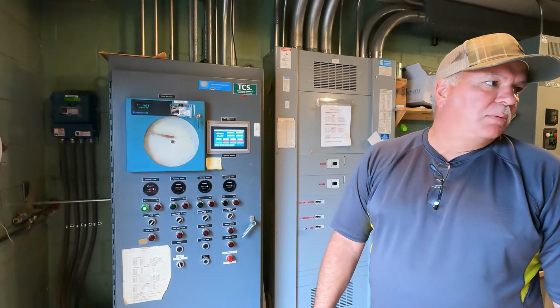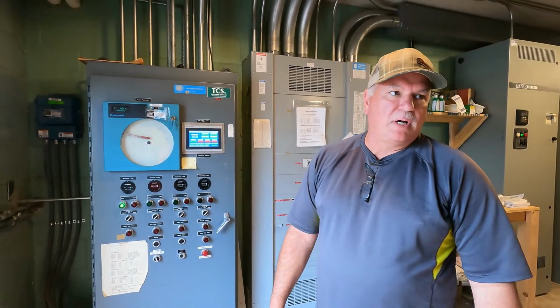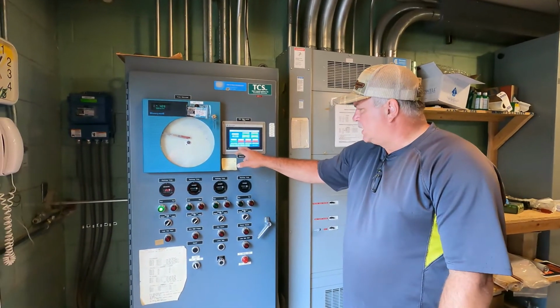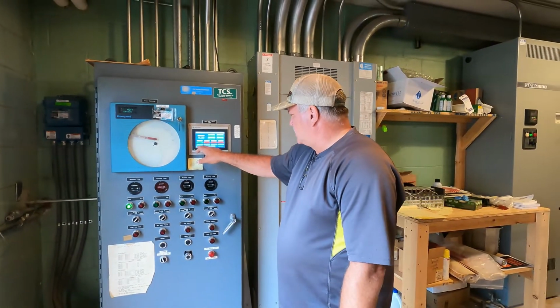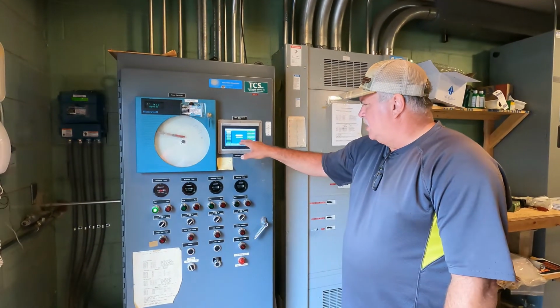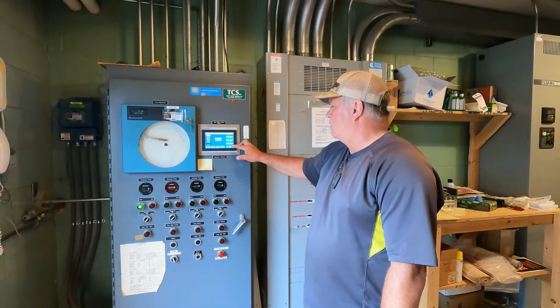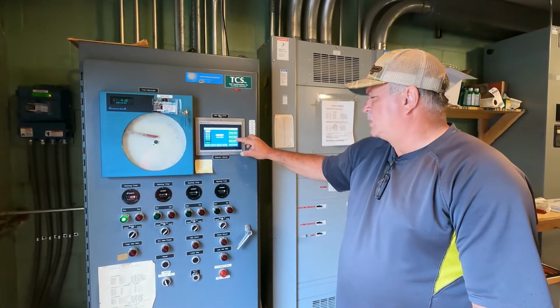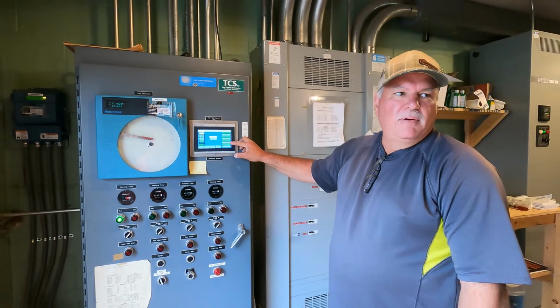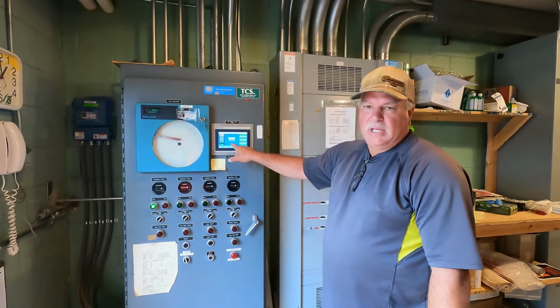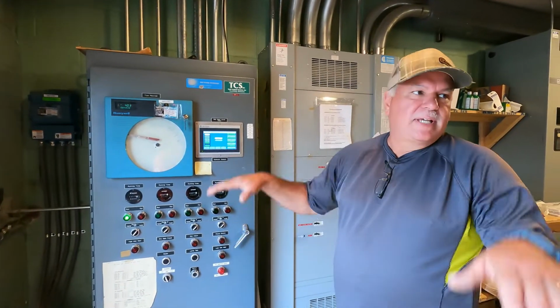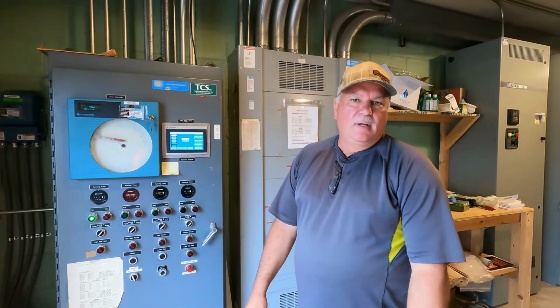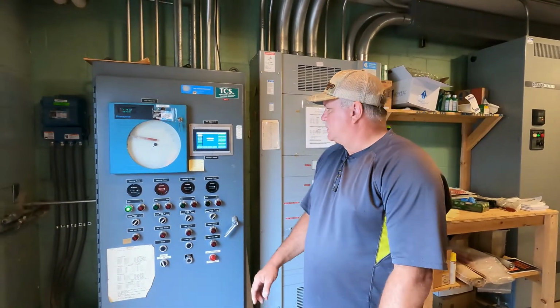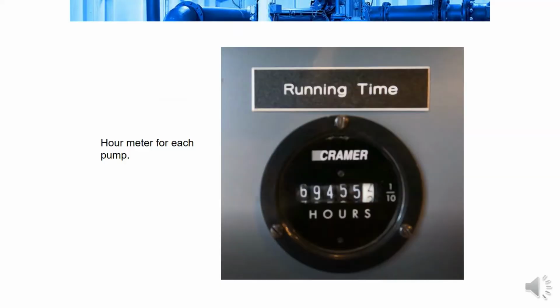Every 6 hours. So the PLC will switch it out every 6 hours. If the flow gets to a certain stage, we would get a step 2 on flow at about 5 feet. So if the level of the wet well gets up to 5 feet, which is currently at 4.1, that would kick the second pump on to maintain level, and so on for all 4 pumps. This is an example of one of the hour meters on the pump control board.